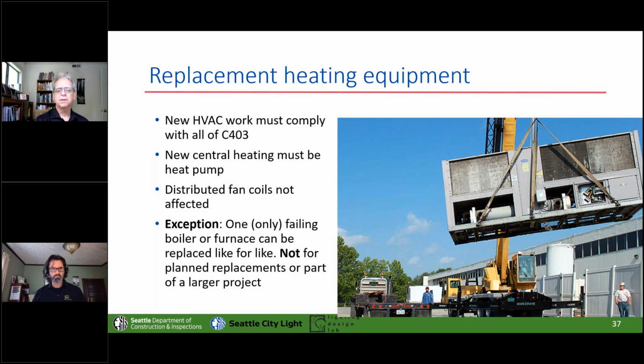We also clarified that if there's an emergency, so you've got a central piece of equipment that is failing and it's January 14th and people are starting to call up and say, what's happening, we're freezing, you can do a one-for-one replacement just with the existing type of equipment. But that doesn't apply to any kind of multiple pieces of equipment or planned replacements.